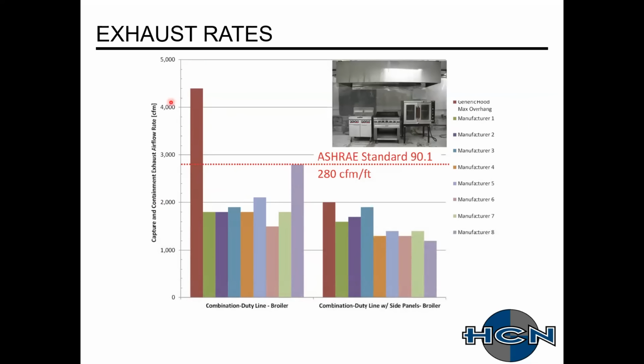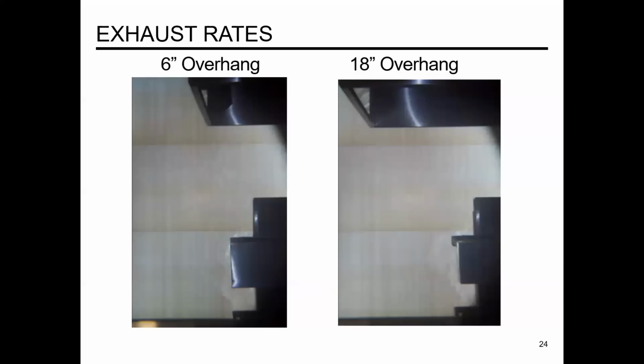The nice thing is if you're taking a look at this and you have a hood that's grandfathered in, they're still having problems and they want to make it more efficient, just adding panels to that generic non-listed hood can improve the capture that much. So when we talk about overhang, again, the big thing is listed. The IMC requires only 6 inches of overhang. And as you can see, this is off of, I believe, a pizza oven. The heat, you can see rising, slowly and surely spilling out, adding that radiant load. Just adding some overhang onto that piece of equipment, you're improving capture and containment of that radiant heat load.